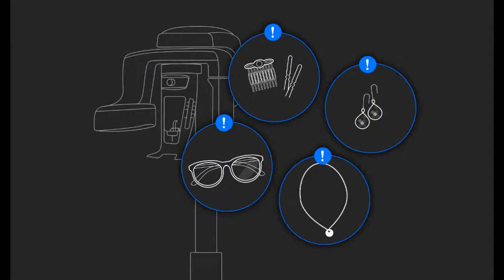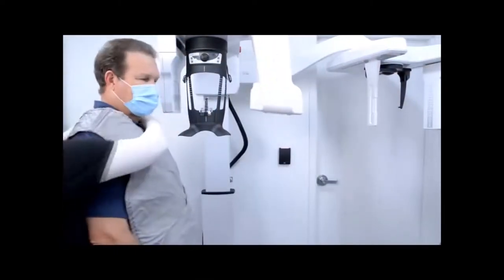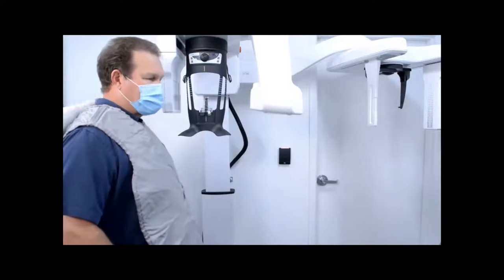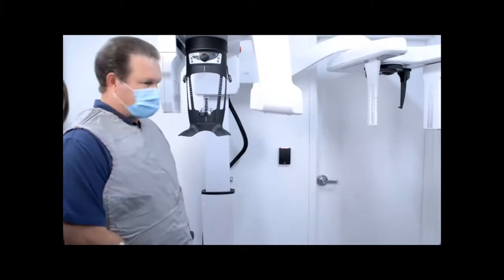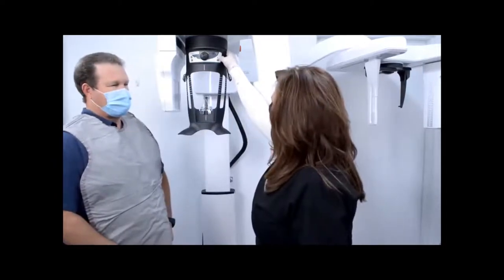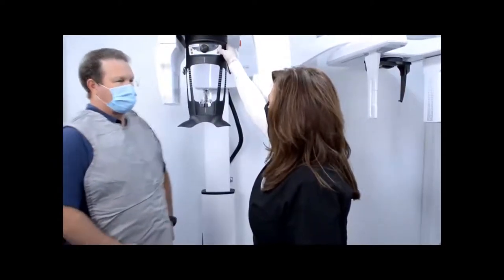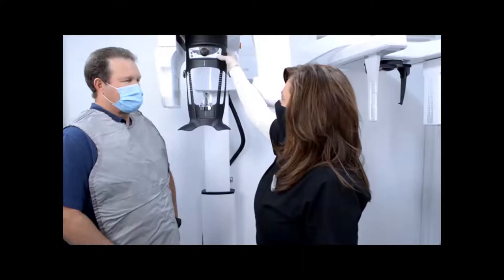Before the patient enters the unit, ask the patient to remove any metal objects above the neck, including jewelry, glasses, hearing aids, prosthesis, metal hair clips, or other metal objects. Place the lead apron on the patient and instruct the patient to stand next to the unit. Next, adjust the unit to the patient's height. The CS8200 3D can be easily adjusted for patients standing or sitting, and is wheelchair accessible.